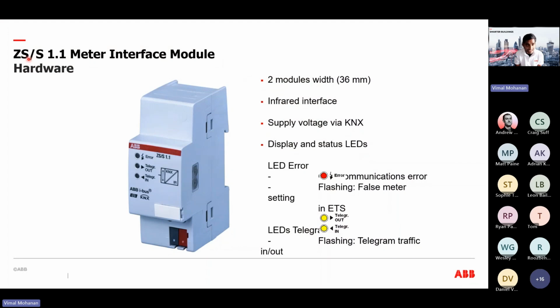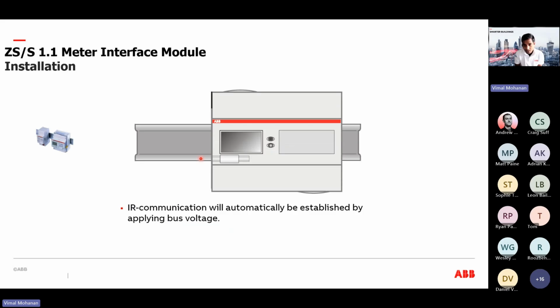If we're talking about the KNX module, it's a ZS/S 1.1 meter interface module. It's a two-module device which has got an IR port on the side. If you are putting our meters in, the ABB series we discussed, you can put the meter in and click on this IR module next to it. By that, all the information in this meter is now coming in and is available in the KNX world.